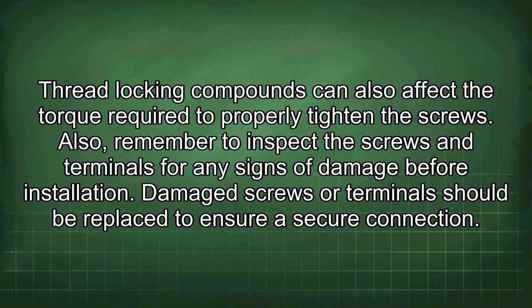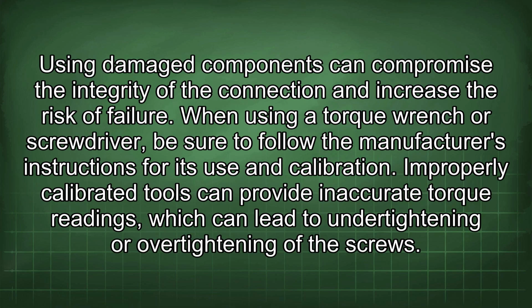Also, remember to inspect the screws and terminals for any signs of damage before installation. Damaged screws or terminals should be replaced to ensure a secure connection. Using damaged components can compromise the integrity of the connection and increase the risk of failure. When using a torque wrench or screwdriver, be sure to follow the manufacturer's instructions for its use and calibration. Improperly calibrated tools can provide inaccurate torque readings, which can lead to under-tightening or over-tightening of the screws.